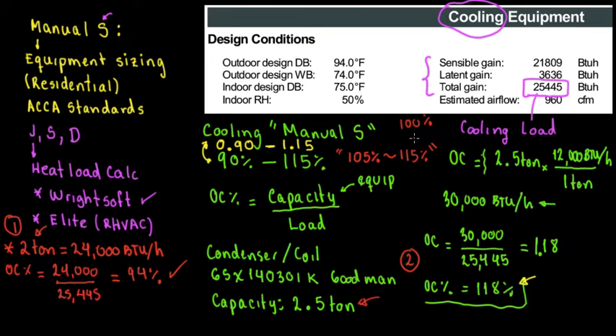Sometimes the refrigerant load charge is not correct, the subcooling is not correct. Sometimes we didn't braze or install with nitrogen so that way we have oxidized this refrigerant, some small particles and then that's going to affect the TXV. So there are a number of factors because of those factors the efficiency of the system is going to decrease. Therefore if you size it for 100% you're not considering those factors and then in summer you're going to have issues. So it's better to be safe than sorry that's why it's better to oversize it a little bit. See it's 118% so I would go for 118%.